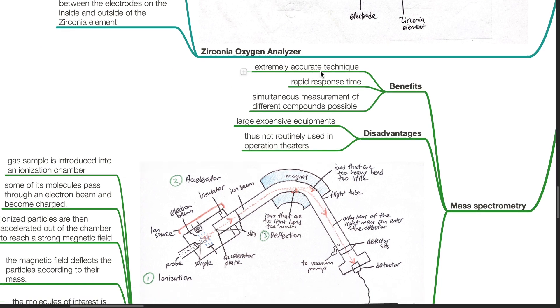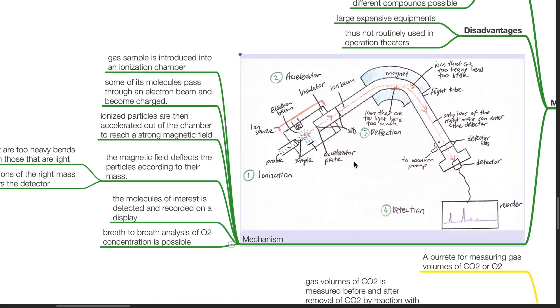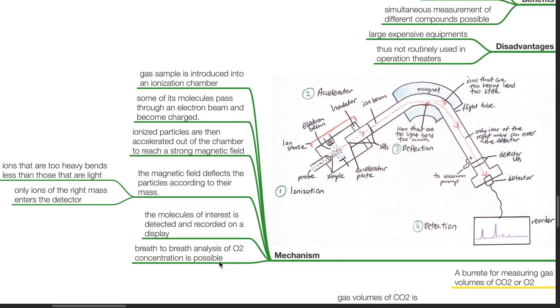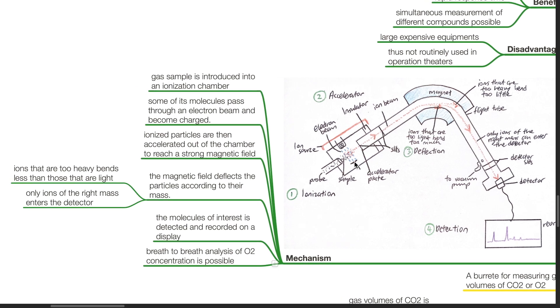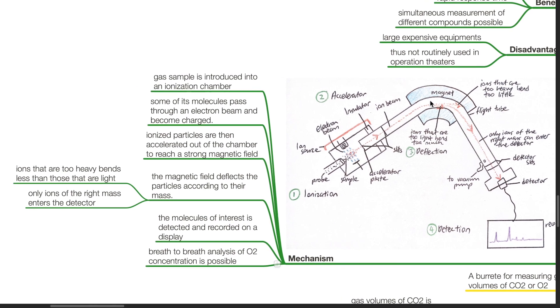Mass spectrometry benefits include extreme accuracy, rapid response time, and simultaneous measurement of different compounds. Disadvantages: large, expensive equipment is used, and thus it is not routinely used in operating theaters. Mechanism of action: a gas sample is introduced into an ionization chamber, some molecules pass through an electron beam and become charged, ionized particles are accelerated out of the chamber into a strong magnetic field which deflects them according to their mass. Ions that are too heavy bend less than those that are light. Only ions of the right mass enter the detector, and breath-to-breath analysis of oxygen concentration is possible.